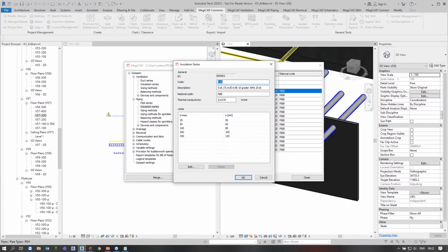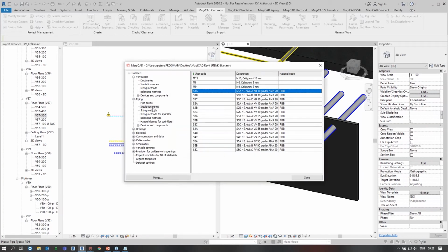So if I use this S1A, then it says that if the pipe size is between 0 and 20, it's going to put 50 millimeters of insulation on that pipe. If I do some sizing, or if I manually change it and the pipe gets bigger, so if it's between 20 and 50, I'm going to have 60 millimeters. So the only thing I have to do is put the right series on the pipe, and if the pipe is growing or shrinking, then MagiCAD is going to change the thickness according to this table. So this is information that we need in the project.